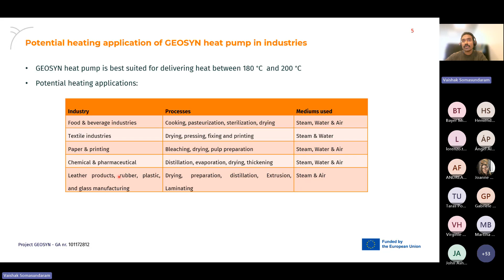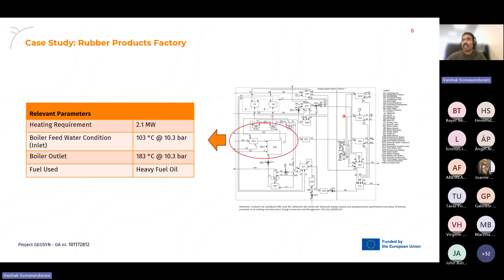In the slide here, the diagram on the right side shows the process flow diagram of a rubber product industry, where we can see there is a steam generating boiler which generates steam at 183 degrees centigrade at a pressure of 10.3 bar. That is, it produces almost saturated steam. The steam boiler input, or the feed water or condensate return temperature, is 103 degrees centigrade and it is heated to 183 degrees centigrade. The steam boiler presently uses heavy fuel oil as the heat source and it has a capacity of 2.1 megawatt. Like in any other industry, the steam which is produced at 183 degrees centigrade and 10.3 bar is then throttled for different applications.